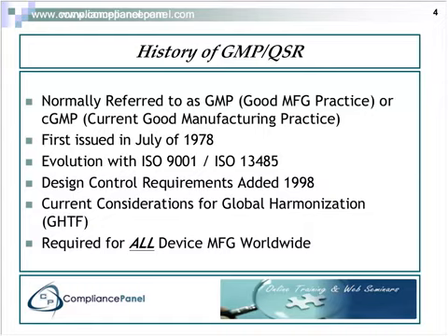So in lieu of having the FDA come in to audit or investigate at your facility, you could have your notified body, as part of your annual audit, do the QSIT audit, and they could submit that to the FDA. And again, this is required for all device manufacturers worldwide who are intending to distribute or market medical devices within the United States.